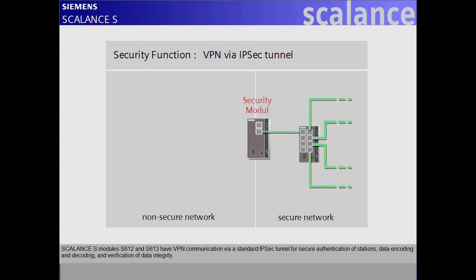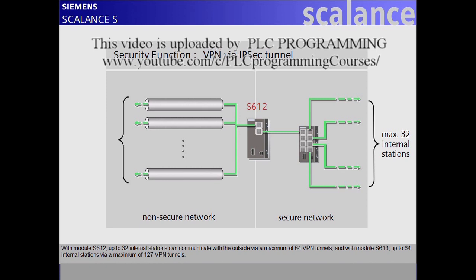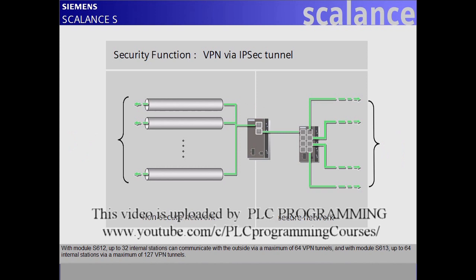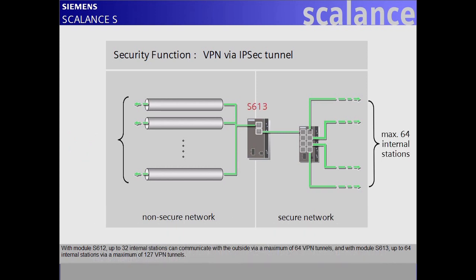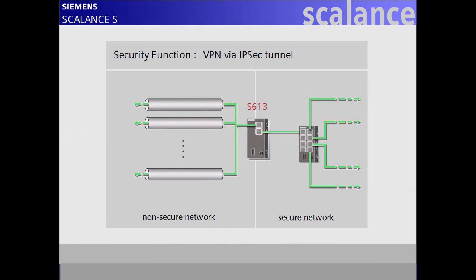Scalance S modules S612 and S613 have VPN communication via a standard IPsec tunnel for secure authentication of stations, data encoding and decoding, and verification of data integrity. With module S612, up to 32 internal stations can communicate with the outside via a maximum of 64 VPN tunnels. With module S613, up to 64 internal stations can communicate via a maximum of 127 VPN tunnels. Both IP messages and non-IP messages, such as layer 2 messages, can be transmitted through the IPsec tunnel.